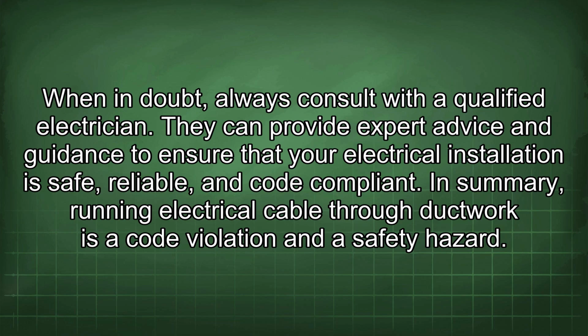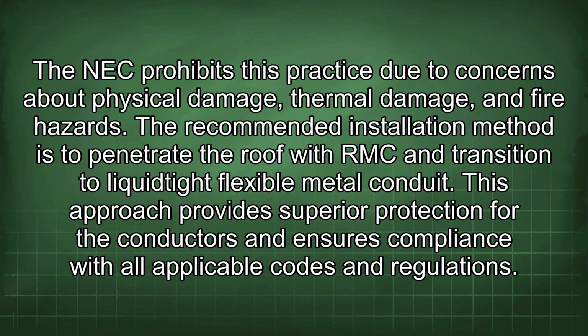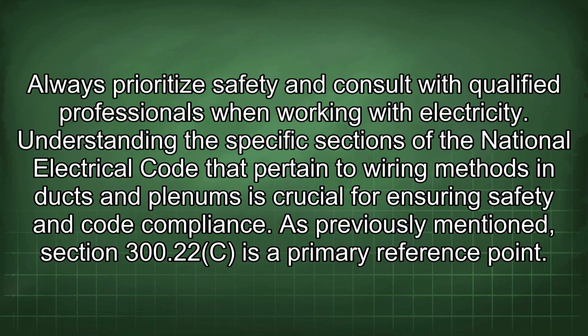In summary, running electrical cable through ductwork is a code violation and a safety hazard. The NEC prohibits this practice due to concerns about physical damage, thermal damage, and fire hazards. The recommended installation method is to penetrate the roof with RMC and transition to liquidtight flexible metal conduit. This approach provides superior protection for the conductors and ensures compliance with all applicable codes and regulations. Always prioritize safety and consult with qualified professionals when working with electricity.